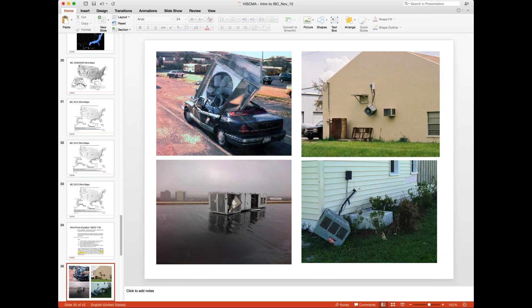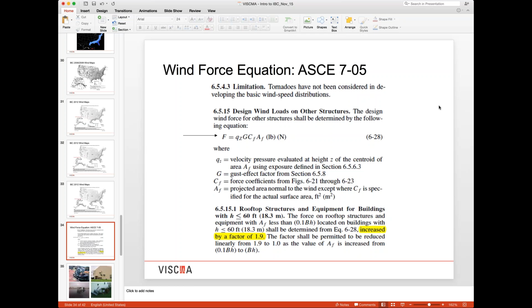Now here are some examples of what happens when it's done wrong. I don't remember where some of these are from, but I know the one on the lower left was from Sandy. The other bad designs, I don't know exactly which hurricane or windstorm they came from, but needless to say they were done wrong. The equipment wasn't attached properly to the building structure. Very similar to suspended equipment and floor-mounted equipment, roof-mounted equipment needs to be attached to the building structure using the equations calculated here to determine the type of restraint or anchorage to the building.